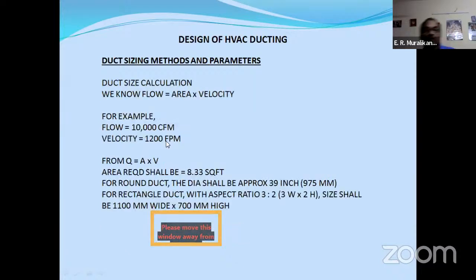Now, duct size calculation. Flow is equal to area into velocity. For example, 10,000 CFM, velocity 1200 FPM, Q equals A into V. Area shall be this much square feet. Round duct is almost 39 inches. And a rectangular duct, if you have an aspect ratio of 3:2, then it will be 1100 by 700. So aspect ratio is also very important while taking the duct sizing. That I will also brief you when we go into the Excel calculation, so you'll be aware of how things behave.